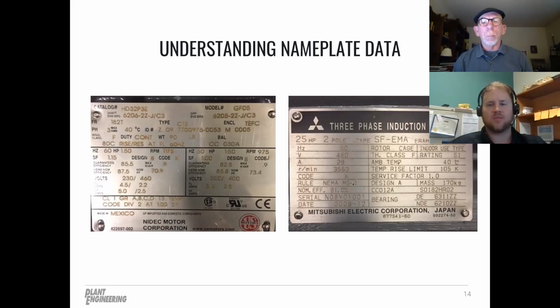Unfortunately, it does get very tough when you're out in the facility and you've got a motor that's 40 years old, or you've got a motor in a very dirty environment, or it's very dark. Carry your flashlight around with you. But it gets tough to read the specifications on some of the motors. So hopefully, when you are working with motors, you can at least find a model number, or maybe you can see a completely legible nameplate. But that's really, in an ideal environment, out in the plant, it just doesn't happen.